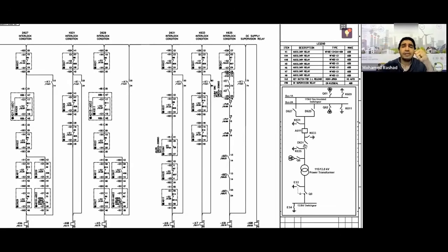So here with the 630, you can't just rely on the air switch being open. I must rely on the fact that the door of this section that I will enter and close must itself be closed. So I need to ensure that the knob switch I'm talking about, or the relay coil I'm referring to in the ABB, or whatever it is, is not in the open position, meaning this section is open. Then I can close the ground. So I need to be sure that it is closed.